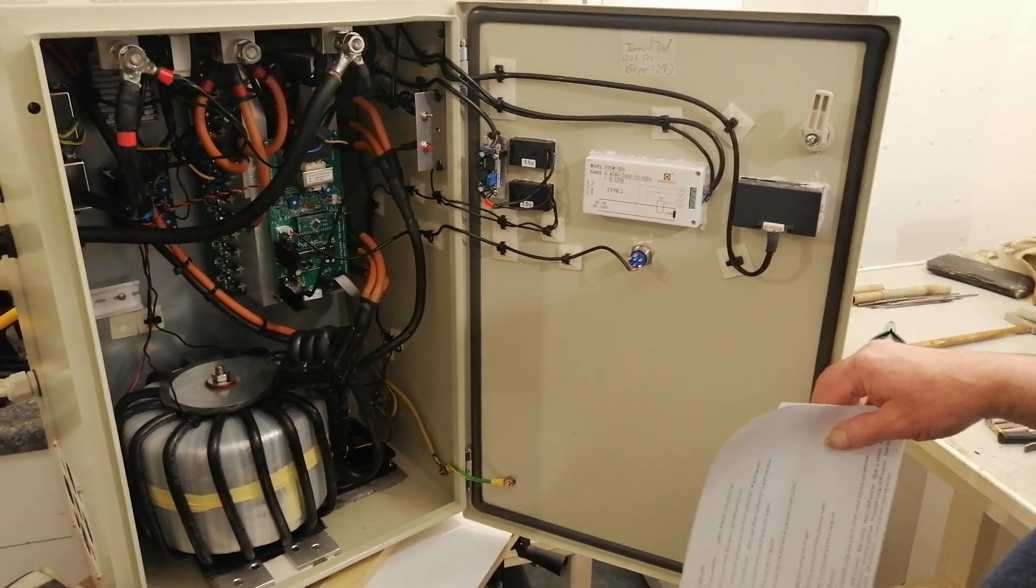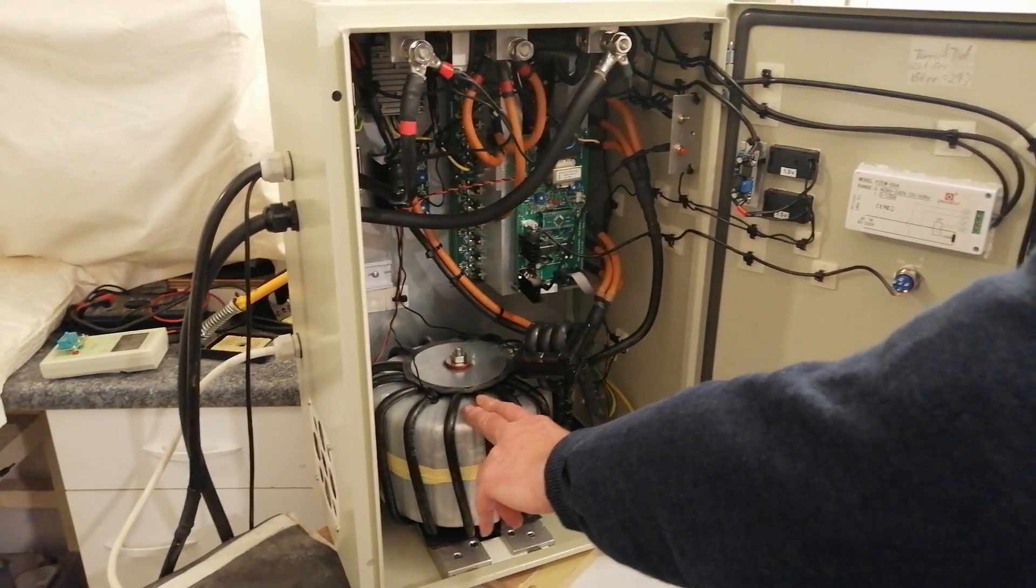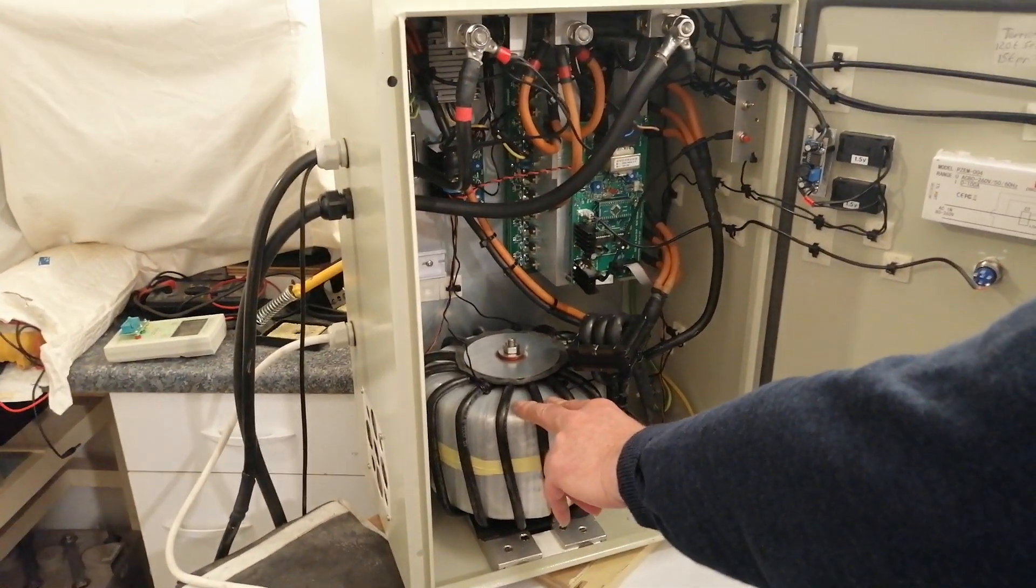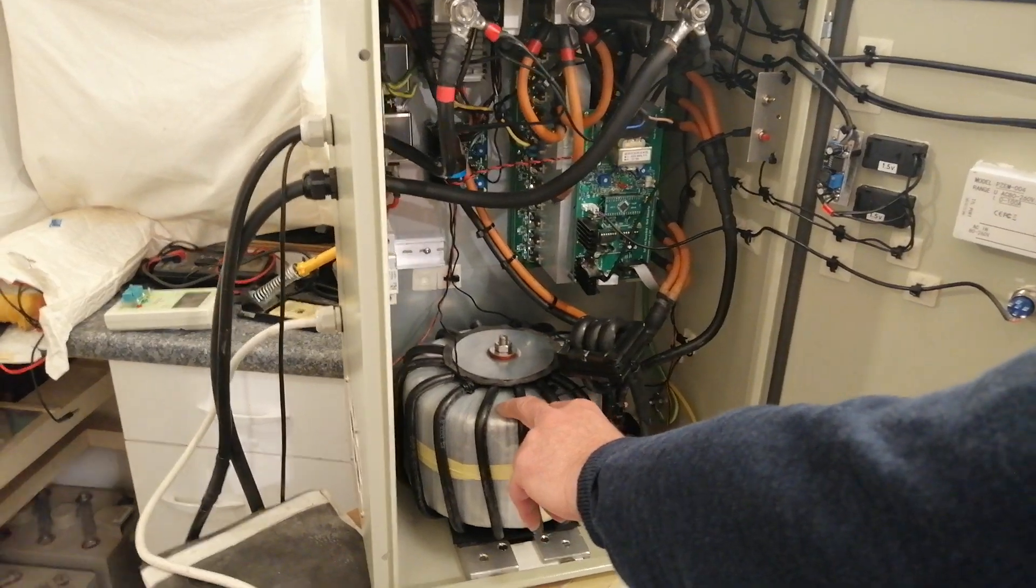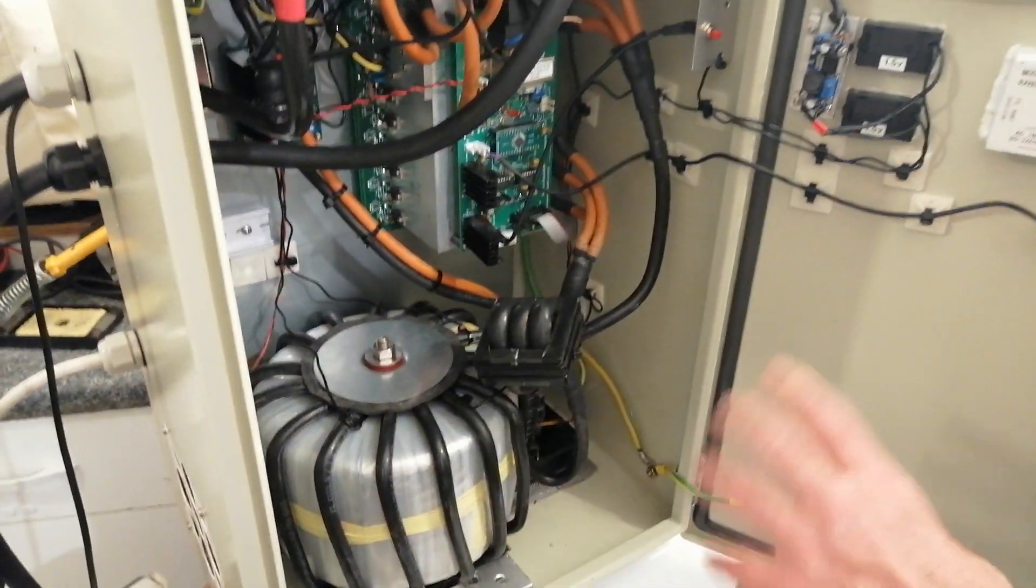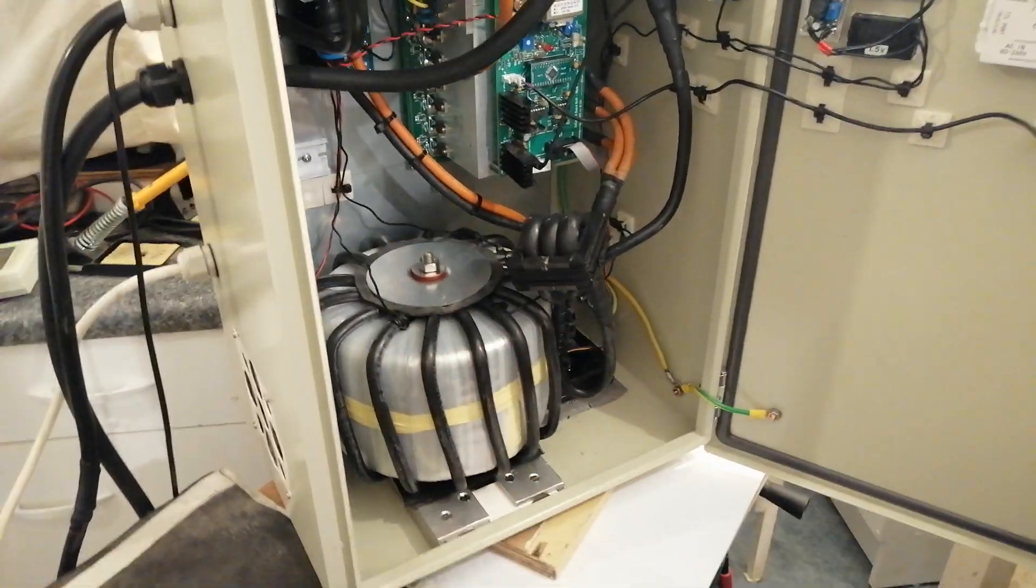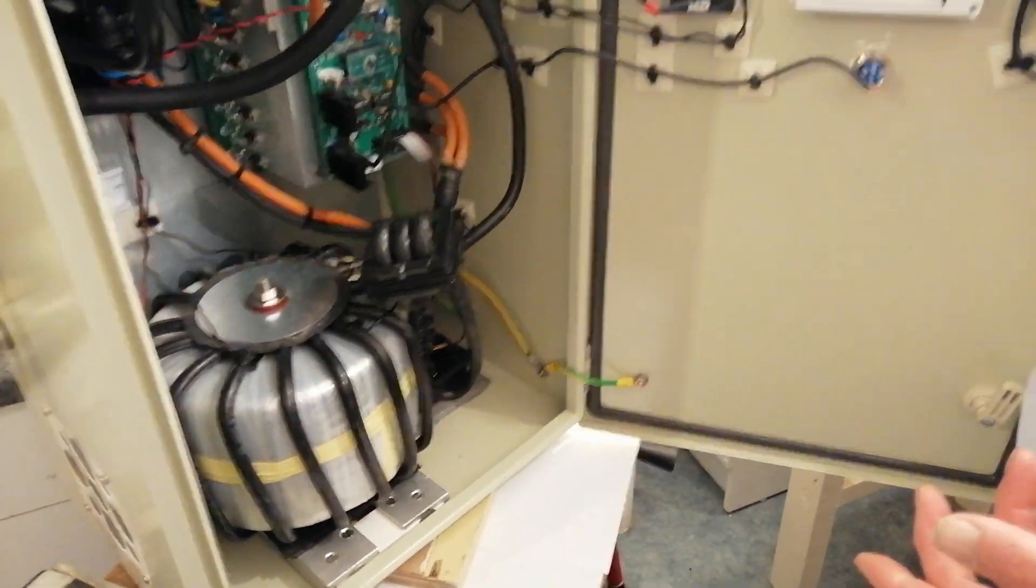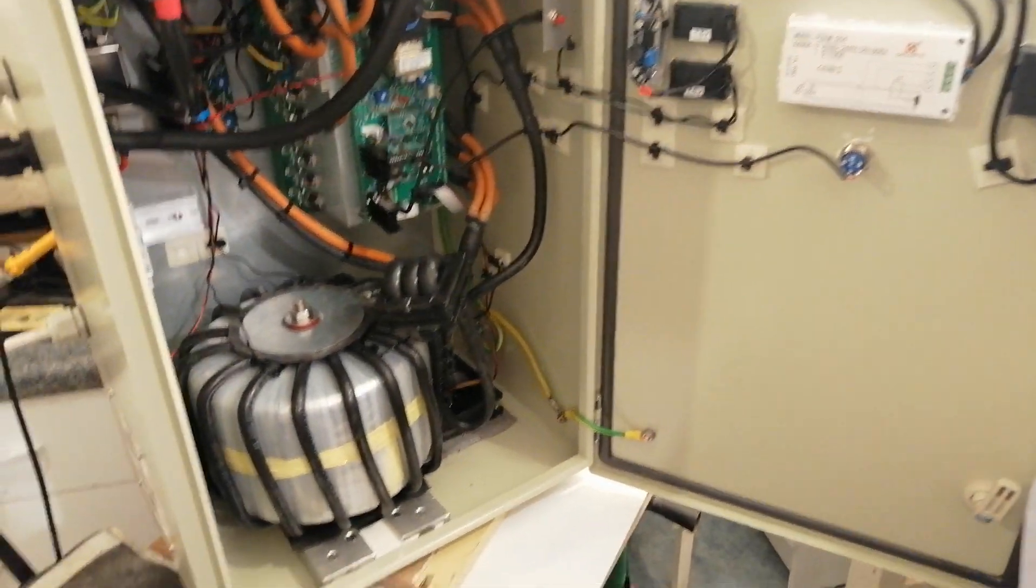I'll start it up in a minute but I'll just point out some of the basic concepts. That's a toroid, 22 kilos core, and it's silicon iron 0.3 thick, basically flat strip bound together to make up the size we want, which is a 100 center hole, 120 high, and 200 on the outside diameter.